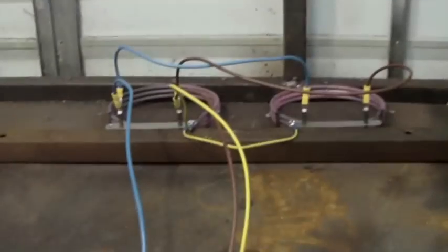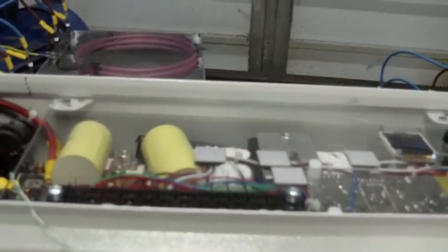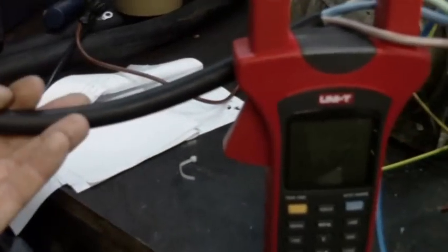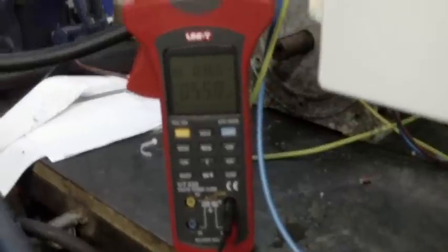And our heating elements are blowing away happily here. We have got some serious heat going on. I am not going to make a huge video on this, just bringing the power up here. We are on the 32 amp supply here, we are running 6 square cable which is warm but not too hot. We have got just over 5.5kW at perfect power factor there, it is zero degree phase angle.